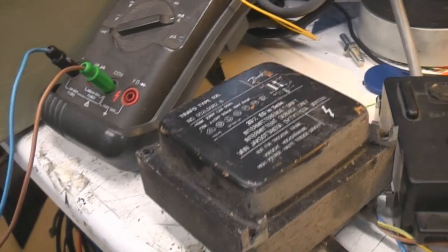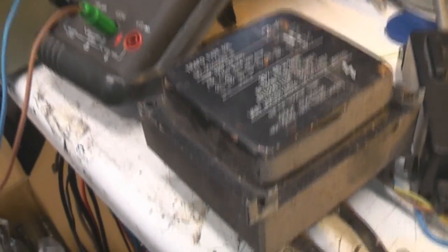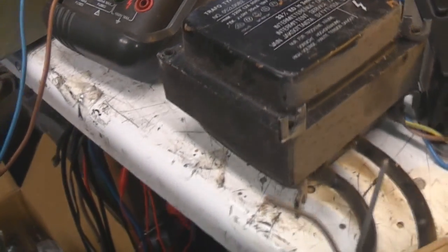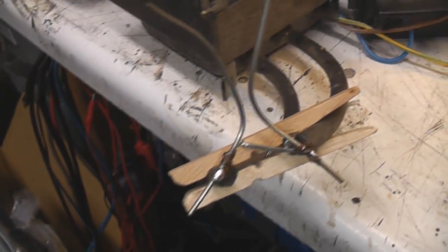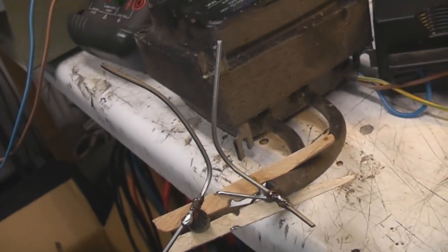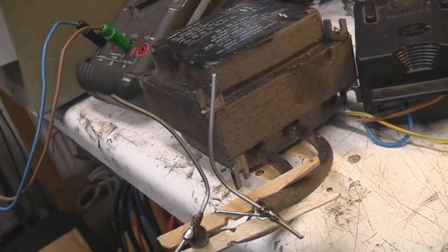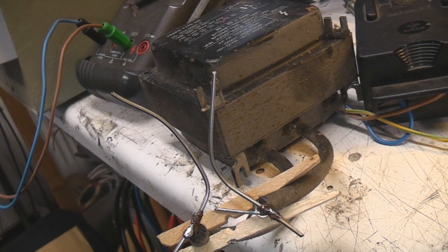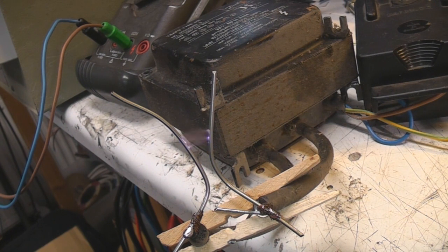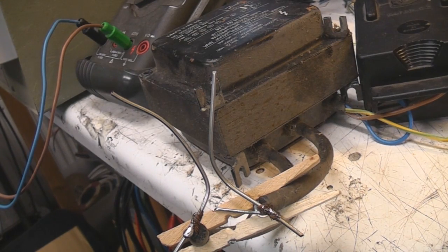Okay, so what I've got here is an oil burner ignition transformer. This puts out about 10 kV at about 20 milliamps. So we can create a nice little arc with that. This sort of quite likes to expand. Let's see what happens if we put that across our breaker contacts.